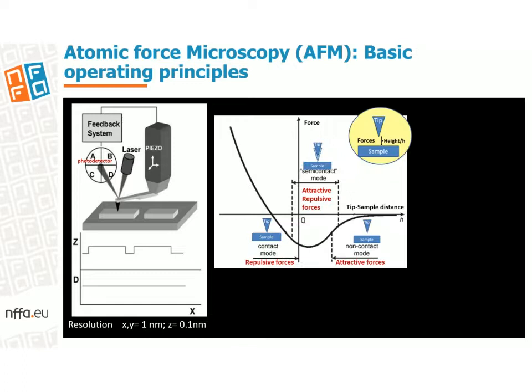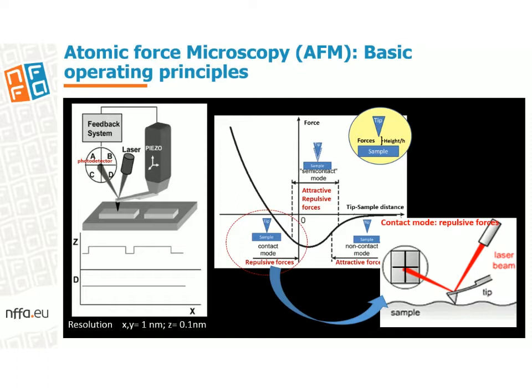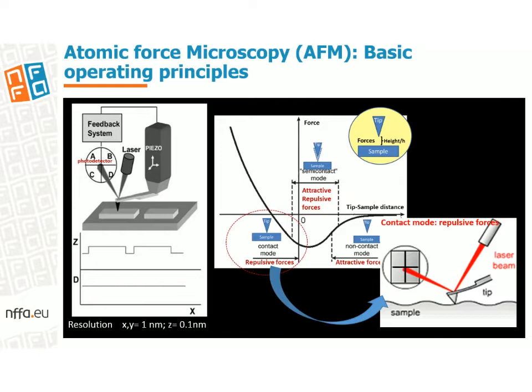Atomic force microscopy was born as a natural desire to extend STM capabilities to non-conducting materials. AFM relies on the use of a tip mounted on a cantilever which is brought into close proximity to a surface, where intermolecular forces acting between tip and sample cause the cantilever to bend. The tip-sample forces are tracked by the deflection of a laser beam focused on the cantilever, which is collected by a photodetector reproducing the sample topography. This technique can also achieve very good spatial resolution and resolve interaction forces with pico-Newton sensitivity in a wide range of environments. The type of interaction force, attractive or repulsive, depends on the tip-sample distance as shown in the slide.